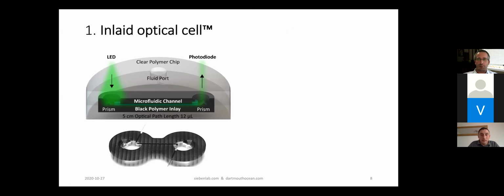And what we do with this, it's much like an inlaid wood table where you take maybe cherry and push it into walnut or something to create ornate tables. We do the exact same thing with microfluidics now, where we take one material, a black plastic say, and push it into a clear plastic. And the trick comes then in how we use that inlay that we've created. We create a channel across those boundaries, which allows us to have portions of our channel clear and transmissive to light, so that we can either couple light into a channel or move light out of a very small channel, and opaque sections that block light that we really don't want from background or stray light.